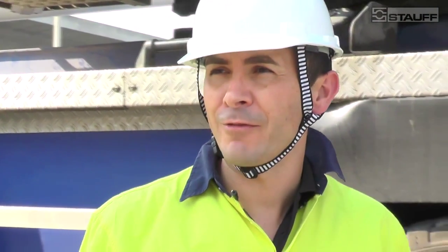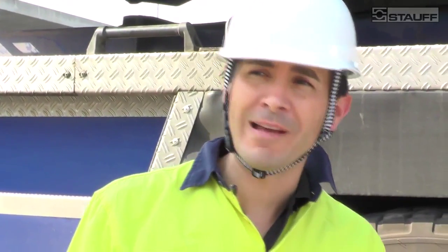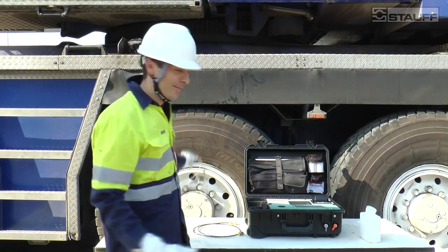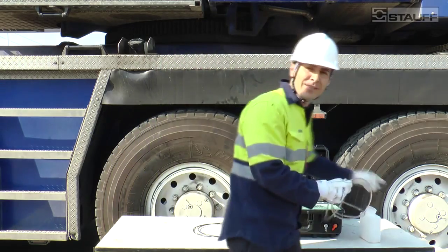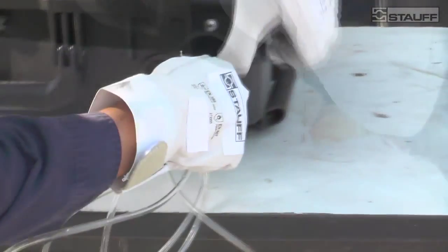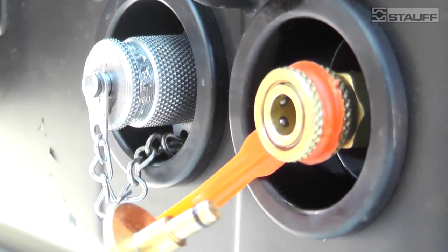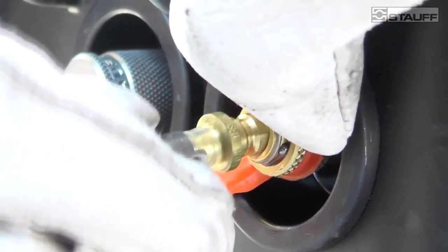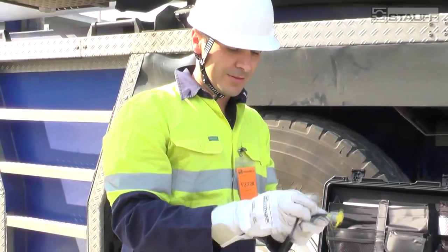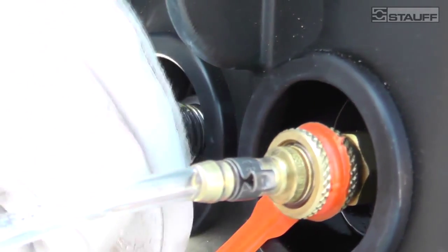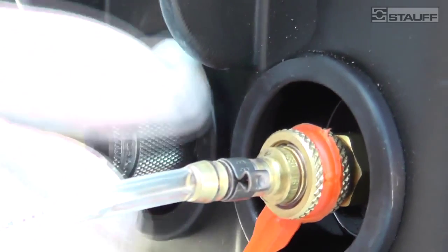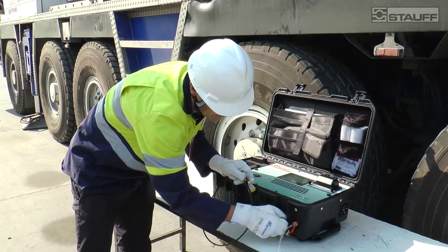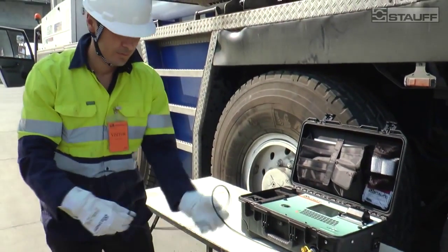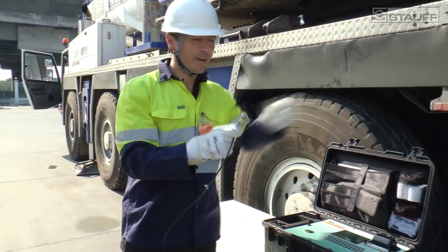Just ensure before you connect that you have no more than 400 bar of pressure in the system or no less than 2 bar. So the first thing is to connect the waste hose into the waste bottle. And then connect the pressure hose into the system. So first you connect to the particle counter, and then connect the other end into the system.